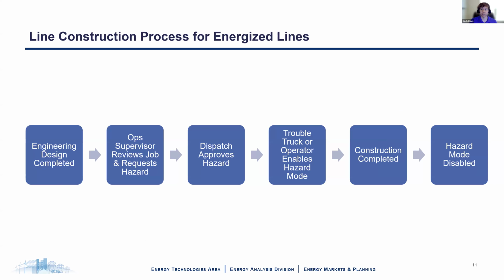The process for doing line construction on energized lines, once you have your engineering design completed, is that it goes to an operations supervisor who will review the job and request worker protection. So a hazard on a recloser, or in this case, since it's energized, just a hazard. Dispatch will review it and approve it. A trouble truck or a system operator will be able to set that hazard mode. So it'll physically get changed either in the field or remotely via SCADA. The construction gets completed and then that hazard gets removed. So that's the general process flow.